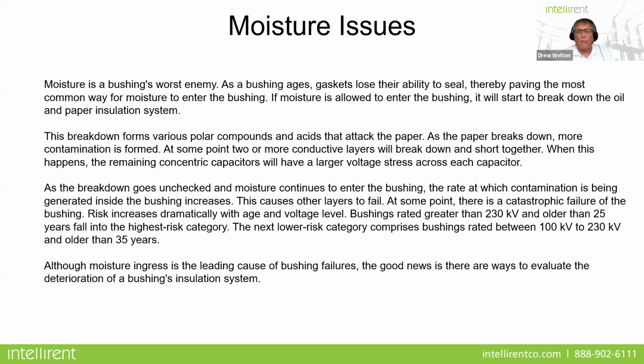And at some point, two or more conductive layers will break down and short together. And then when that happens, the remaining concentric capacitors will have a larger voltage stress across each capacitor. So as the breakdown goes unchecked and moisture continues to enter the bushing, the rate at which contamination is being generated inside the bushing naturally is going to increase. That causes the layers to fail. And at some point, there's going to be a catastrophic failure of the bushing. So your risk increases dramatically with age and voltage level. So bushings rated greater than, let's say, 230 kV and older than 25 years fall into this highest risk category. And the next lower risk category comprises bushings between 100 and 230 kV, older than 35 years. So the higher the voltage rating of the bushing, the longer it's been on the transformer, the more susceptible it's going to be to moisture contamination.